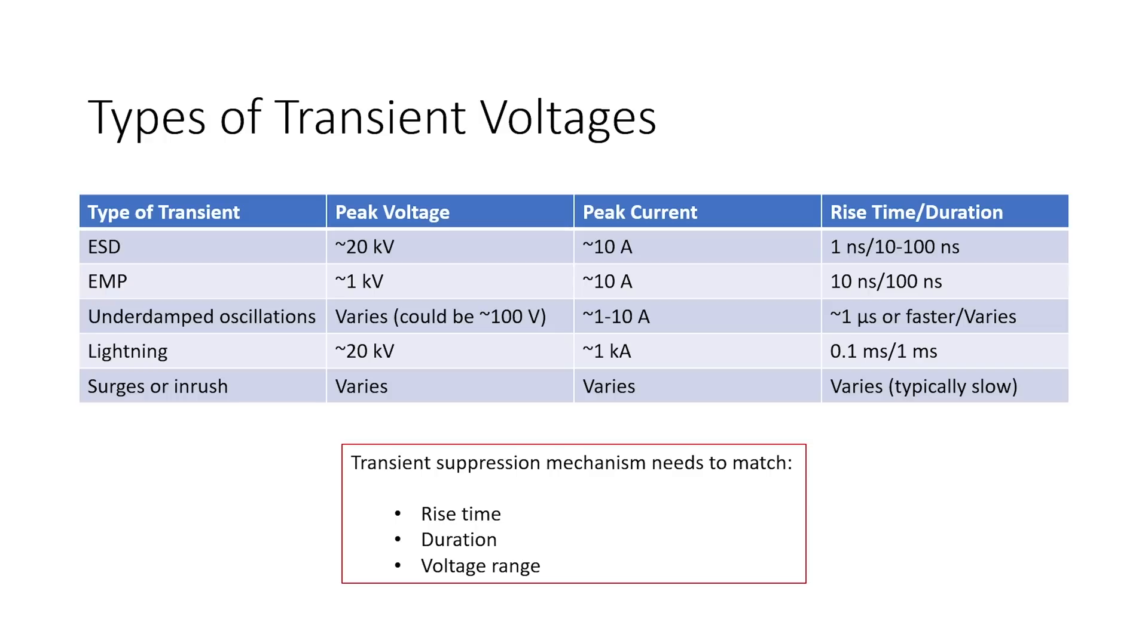As you can see from the very top of this table, ESD has a pretty fast rise time. These are about order of magnitude, so it could be slower than one nanosecond or faster, but in general it's roughly order of magnitude of a nanosecond rise time. Then you have EMP, you have underdamped oscillations like a transient that's excited during switching action. Then you have lightning, and surges or power inrush, and those can vary pretty greatly. The peak voltage, peak current, and the rise time and duration can all vary pretty greatly.